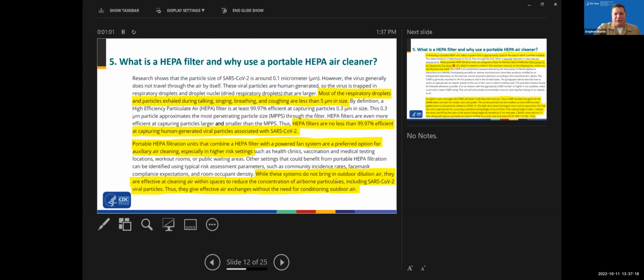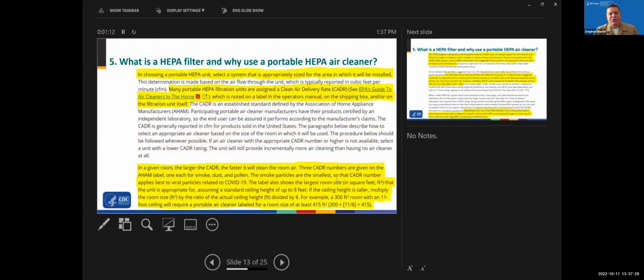Portable HEPA units are essentially just a fan with a HEPA filter. They're meant to be put into a space. They not only help filter the air, but they help increase mixing within a space. When you choose portable HEPA units, we recommend you use the clean air delivery rate method. The link to EPA's guide is there. Essentially, that's a test method from AHAM that gives you two numbers. They'll give you a clean air delivery rate, and then we'll do a calculation based on the room size, in square feet, that your air cleaner would be good for. You need to keep in mind that this does assume an 8-foot ceiling. So if you're putting an air cleaner in a tall space, you need to do a calculation to adjust that. We go through that in our FAQ number 5.